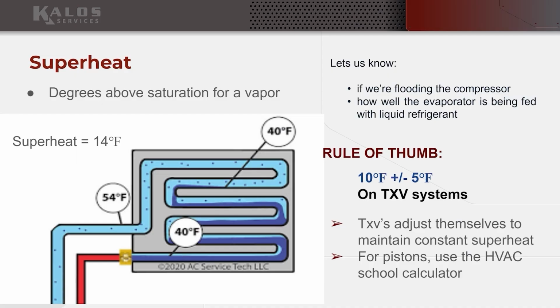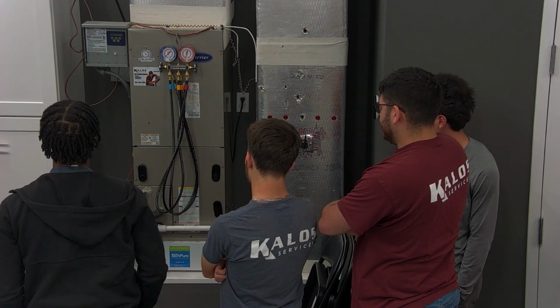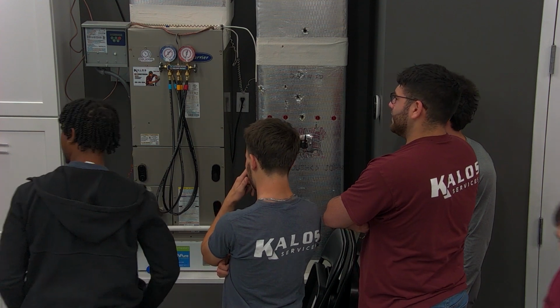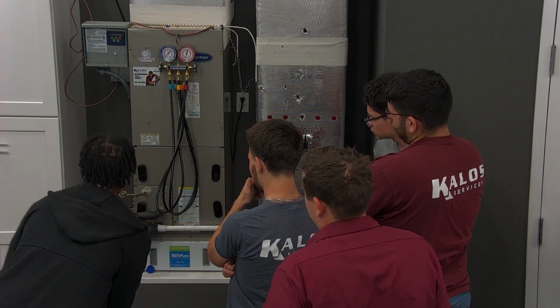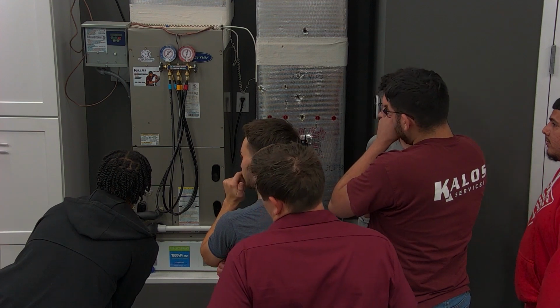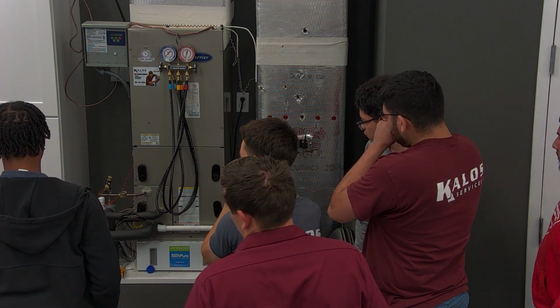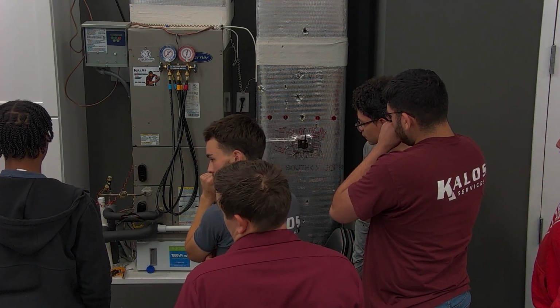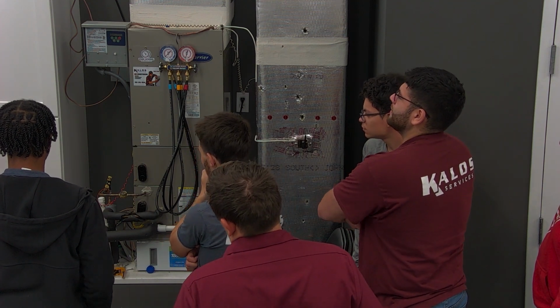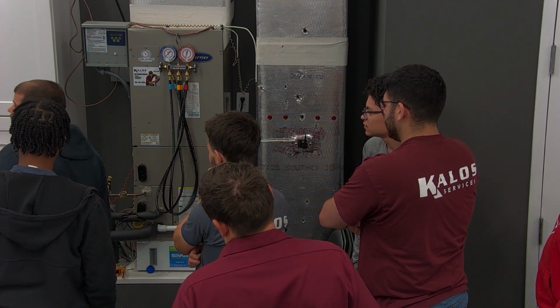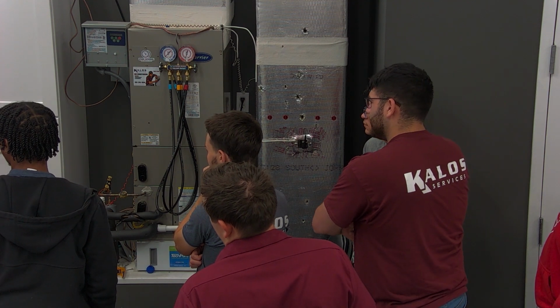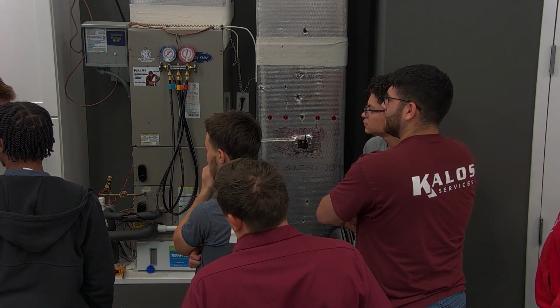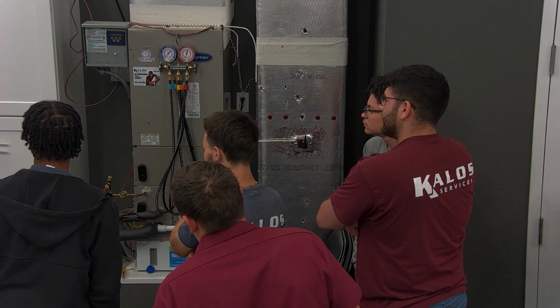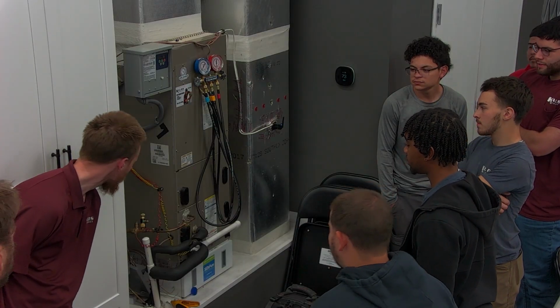Can we measure our superheat right here? Is there a way to measure superheat without the clamp? No, not without the clamp. We're going to use those two clamps. How did you do it? On the suction line. Is there a port for it? There is not. You can't. So he says we can't measure superheat. Did everyone agree with that?